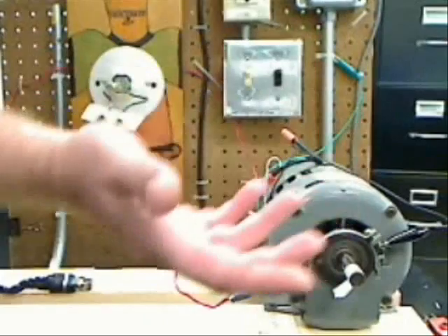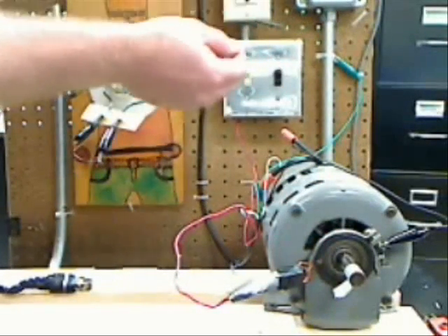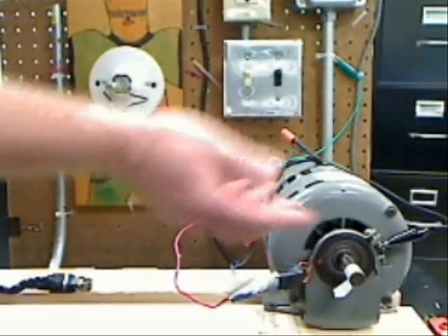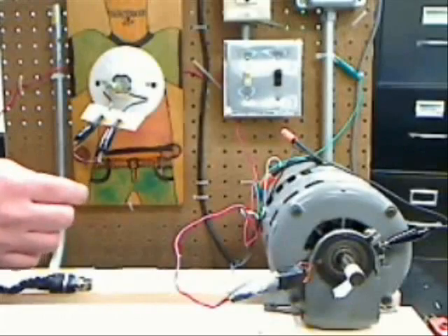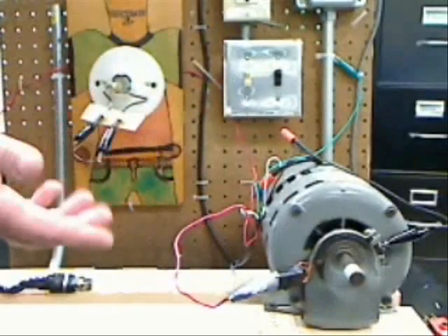So the breaker did its job and tripped open. We have a device, let's say refrigerator, ungrounded. Ungrounded because somebody used an adapter or cut off that third prong which is ground. The hot leg is worn due to vibration. It's touching the frame of that device. We didn't get a breaker trip because of the removal of ground. So this system runs just fine.